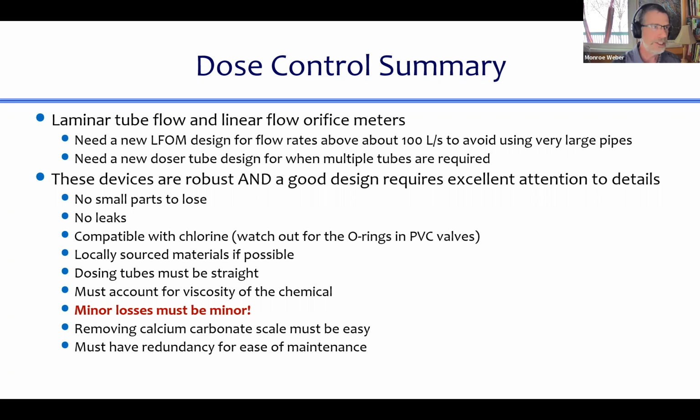And just drilling this home, minor losses have to be minor in this system, because minor losses go with the square of the velocity, and we want the linear system. And chlorine is going to deposit calcium carbonate, so that has to be easy to clean.